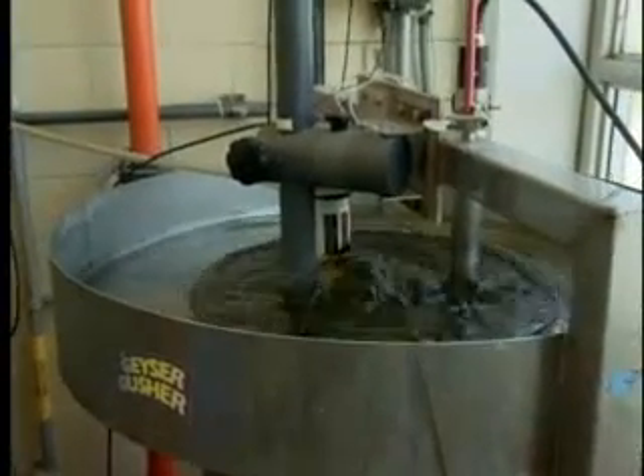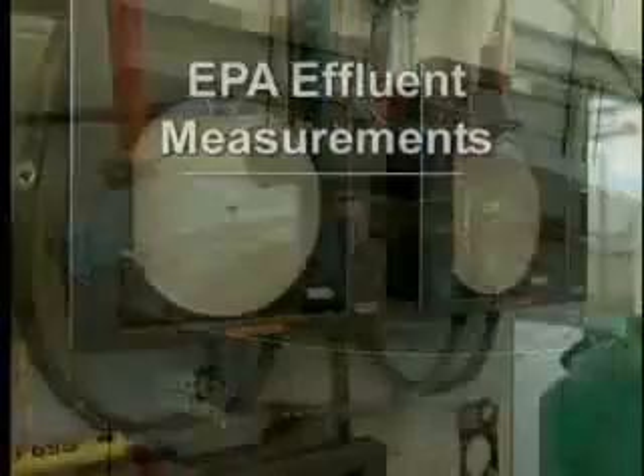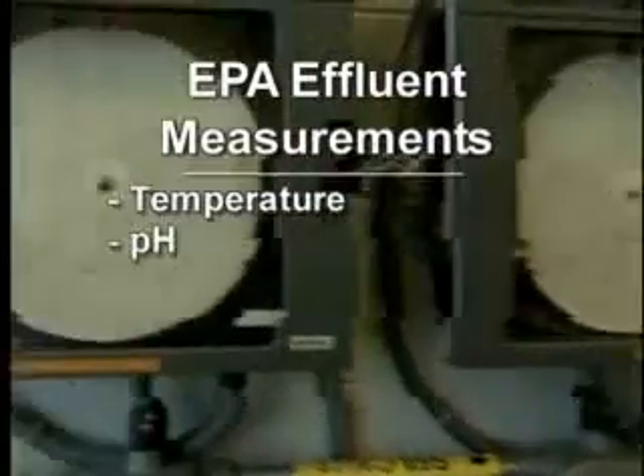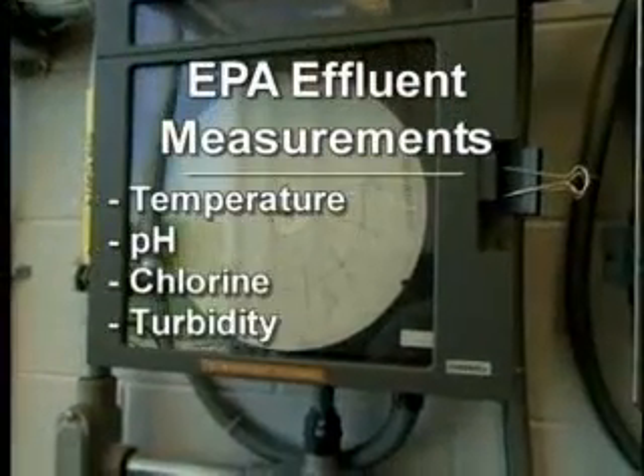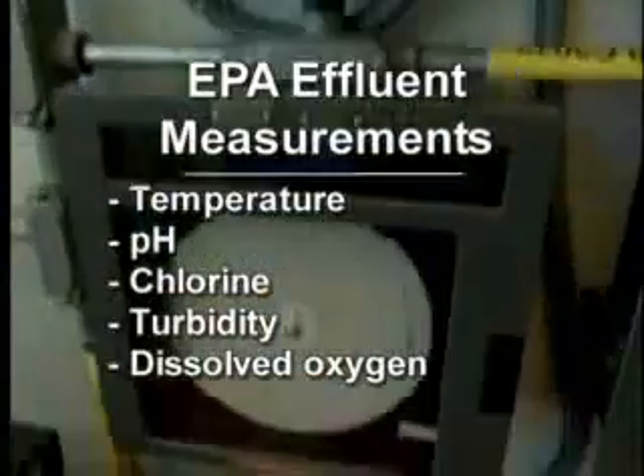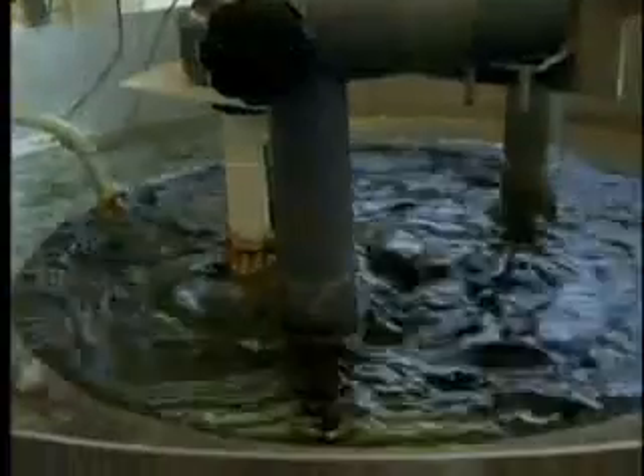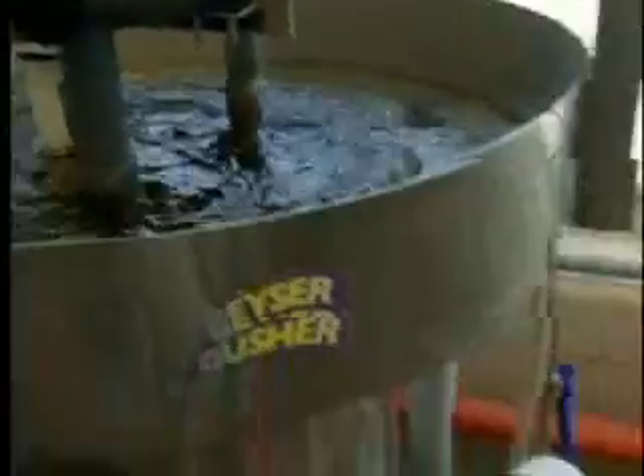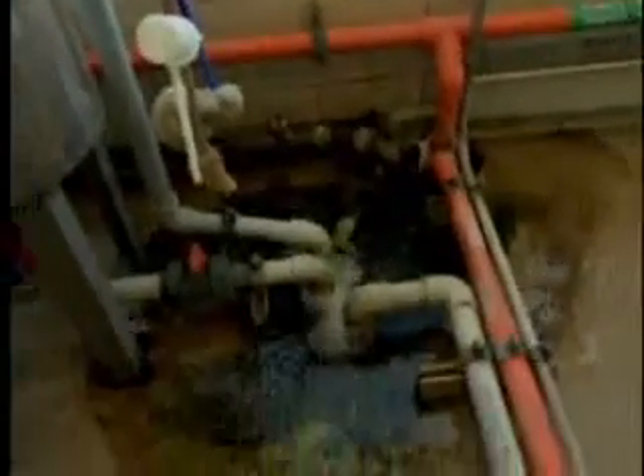For ourselves and for the EPA, we're measuring all kinds of parameters in the effluent as it goes out. We measure temperature, pH, chlorine, turbidity, dissolved oxygen, ammonia. So this is where we monitor the effluent before it goes to the river. And here it is. Water once full of waste and contaminants returns to the river environmentally safe. It's hard to believe that water that once looked like this now looks like this.